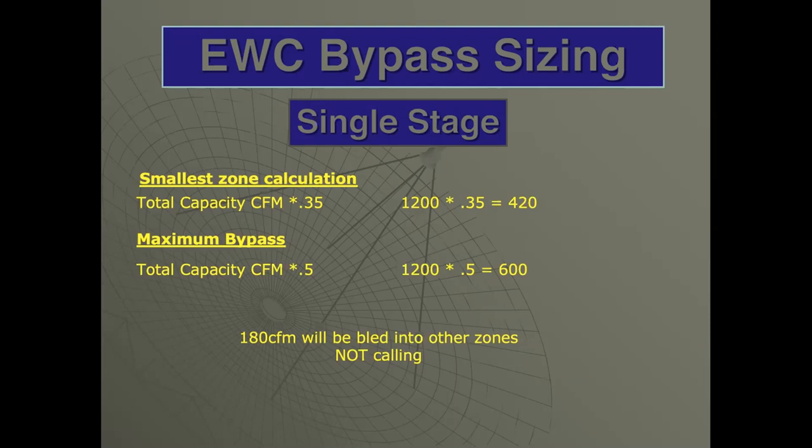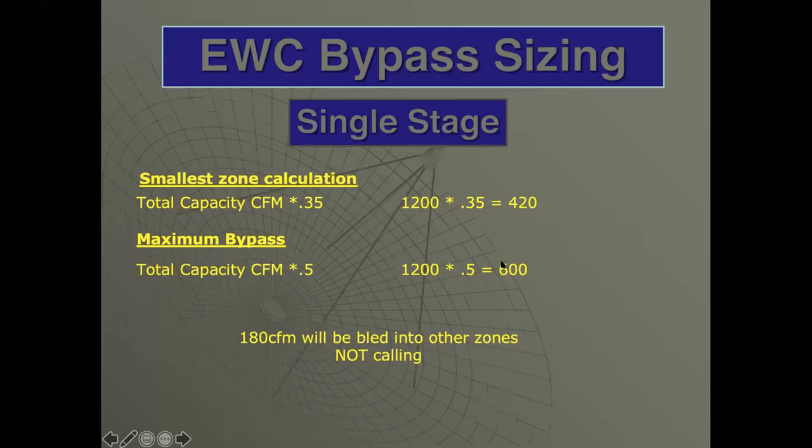In our situation here, a perfectly designed, sized, and set up bypass, we saw, will increase the efficiency of every air conditioning system out there, dehumidify better than anything, and deliver air better than anything. Now when I'm using this factor, I'm going to make sure I'm doing everything I can to not have that duct sweat. Again, if you have questions on this math, by all means bring them up at the end or email me, text me, call me, whatever you want to do.